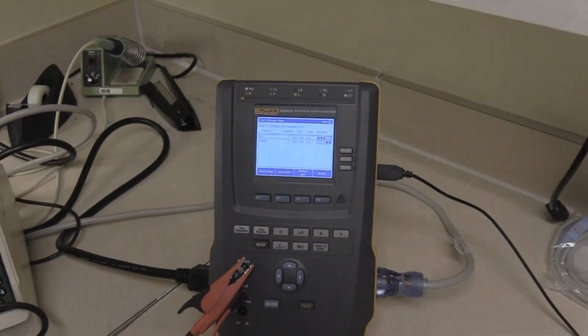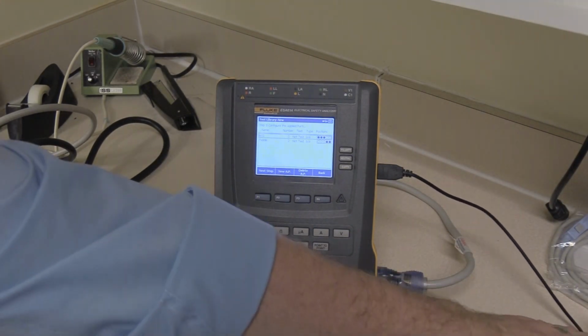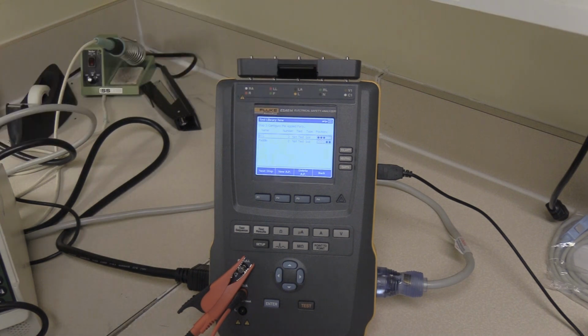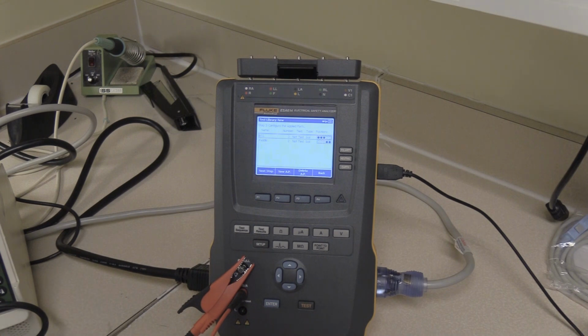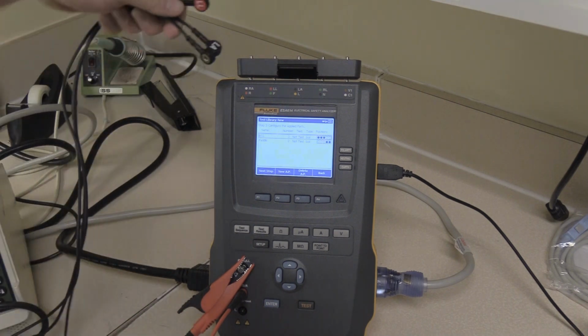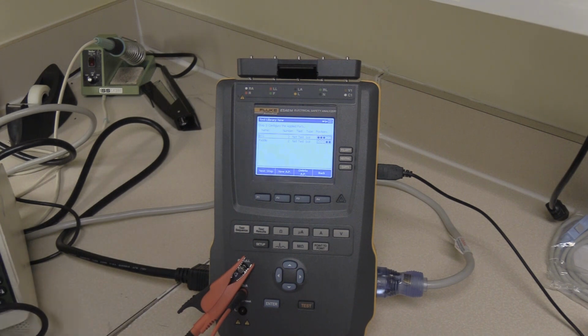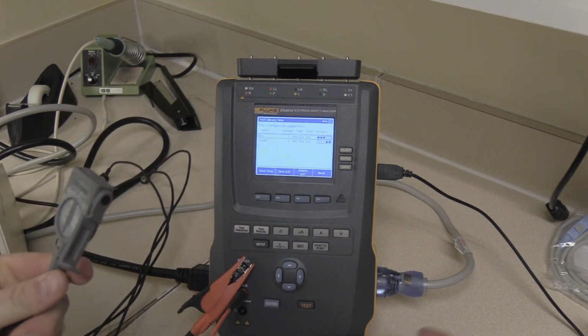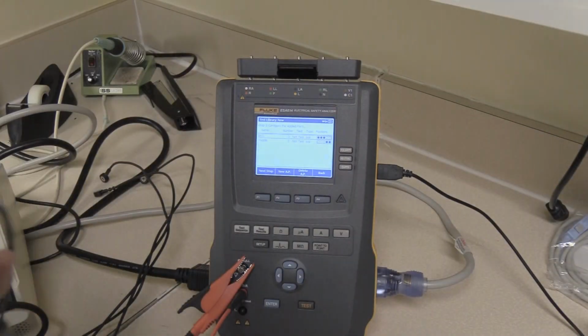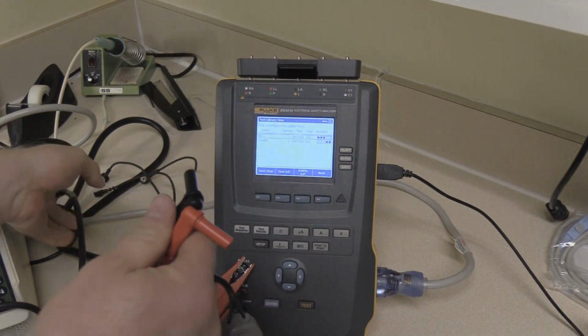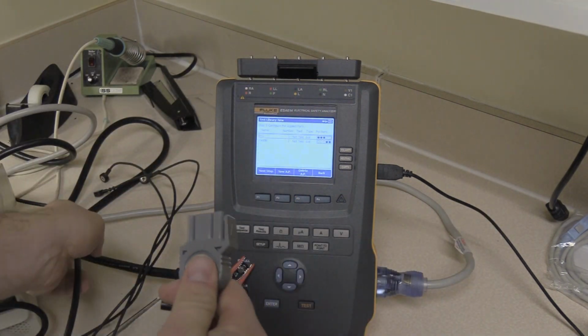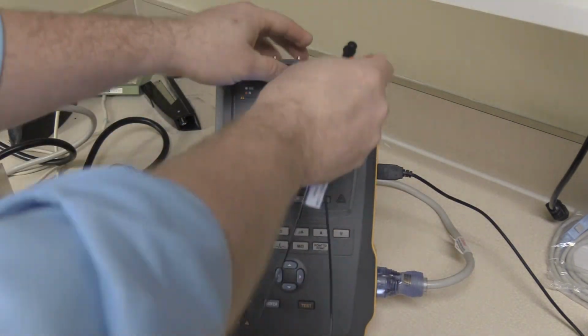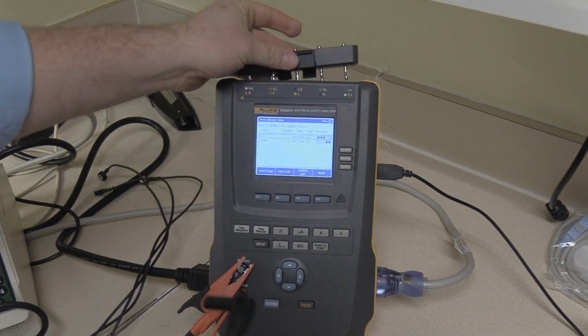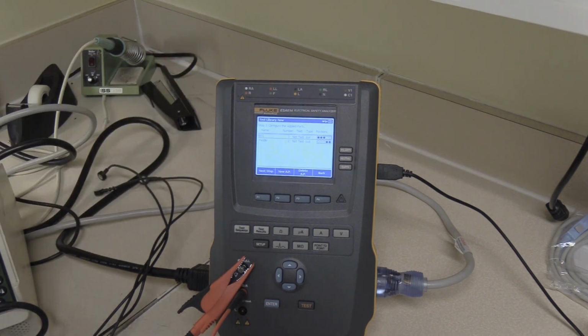But what we're going to need to do, because the LifePak20, when you plug in the adapter on the top and put the leads across there, here's the 3rd one, put 3 leads across the top, you notice that the last 2 ports are also taken up and there's no place to plug in a hands-free adapter. To do that, we use the adapter from the Impulse 7000 and connect it to the hands-free port, but the ends are banana pins and the snap adapter takes it up, so we can't use this portion either. So let's go ahead and modify how we're going to connect the applied parts.